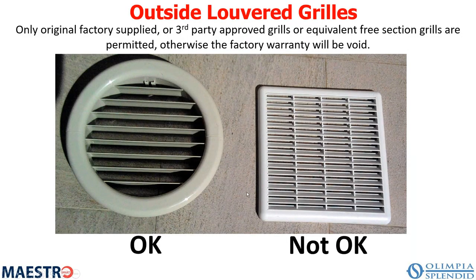This is an actual job that we ran into that had failed, where the contractor decided to use a different grill than what we supplied, and it didn't work out in his favor. Because you can see the free area of this grill did not match that. So he actually had to take those off and change them. But we are currently working with two grill manufacturers to get us either two rectangular grills, which some people like, it fits into their building better. So it'd be a rectangular for the intake and a rectangular for the exhaust. But I might also get one that is just one rectangular grill that covers both intake and exhaust. So we're looking into that as well.